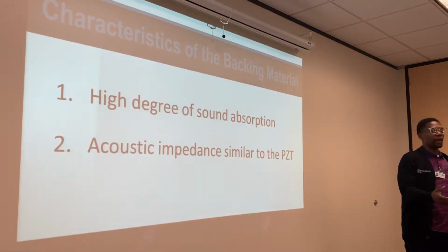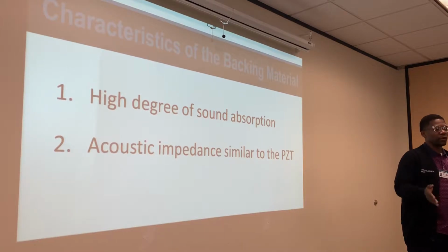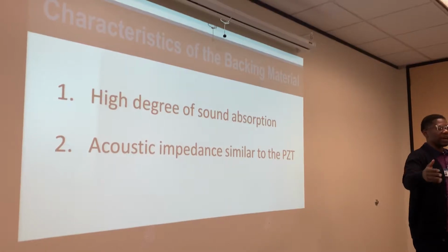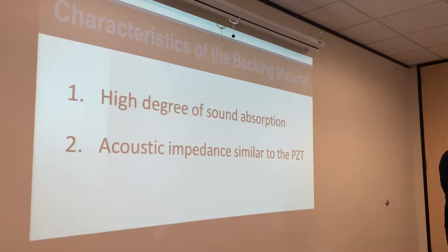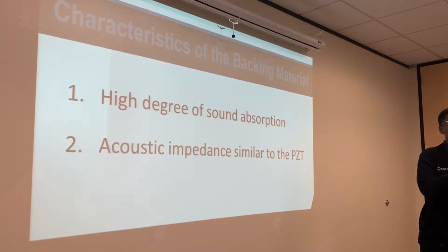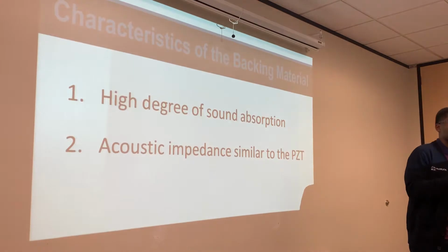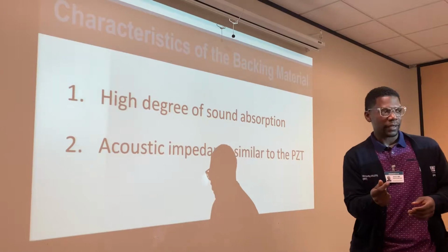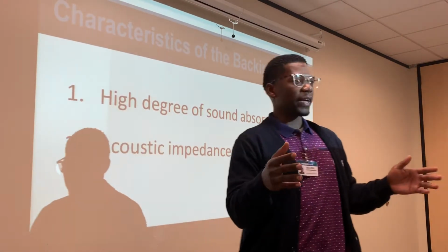So if both are 5 transducers, the wide bandwidth one is going to operate at a wider range, but the narrow bandwidth one is going to mostly operate at the 5 frequency or a narrower range of frequencies. Also, that has to do with continuous versus pulse wave. We use pulse wave transducers, and you're on the right track, because we do like short pulses. The damping material stops the vibrations, but it's not going to stop immediately, so it's going to operate at a wider range of frequencies.